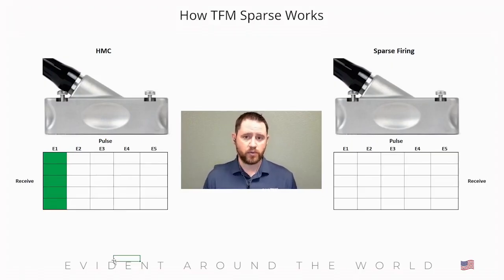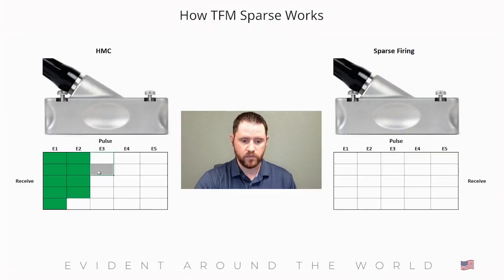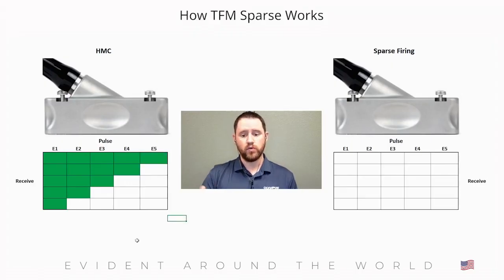In a half matrix process, each time you pulse the next element within the sequence, you remove the reception element that's already been pulsed. And what that does is it reduces the amount of sound waves that are being received, thus reducing the amount of data that's being fed to your acquisition software or to the instrument. So what this ends up looking like is as we pulse each element, we drop off a receiving element. Thus, you get half of the data set. And this process works fairly well when you are attempting to send the raw data to another device.